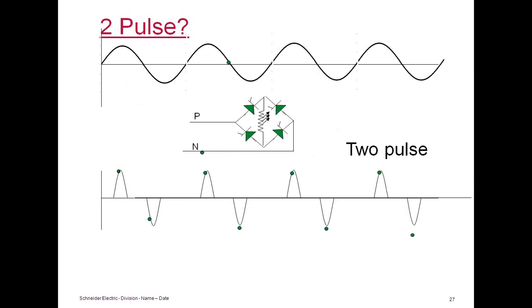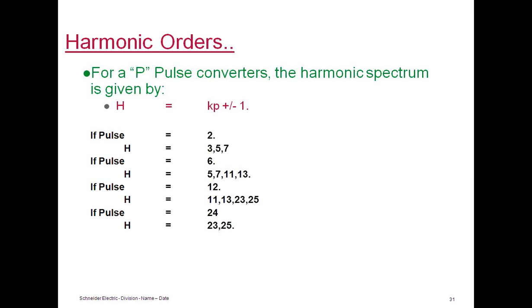It's very important for us to know the number of pulses because the harmonic spectrum depends on it; the harmonic orders depend on what kind of load it is. The classic example of two pulse converters are SMPS loads, used in all laptops, computers, LED lamps, and so on. There are some rules, sort of mathematics, for what kind of pulse gives what kind of harmonics. The formula is kp plus or minus 1. Any two pulse device will give more 3rd and 7th harmonics. A 6 pulse device will give the 5th and 7th, with the 11th also dominant in the spectrum. A 12 pulse gives the 11th, 13th, and so on.